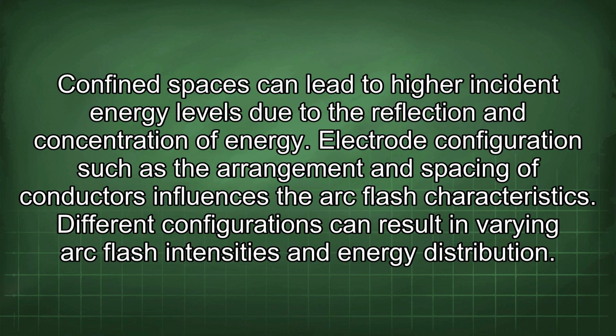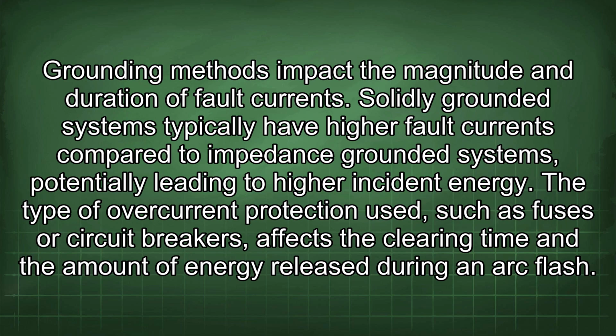Electrode configuration, such as the arrangement and spacing of conductors, influences the arc flash characteristics. Different configurations can result in varying arc flash intensities and energy distribution. Grounding methods impact the magnitude and duration of fault currents. Solidly grounded systems typically have higher fault currents compared to impedance-grounded systems, potentially leading to higher incident energy.